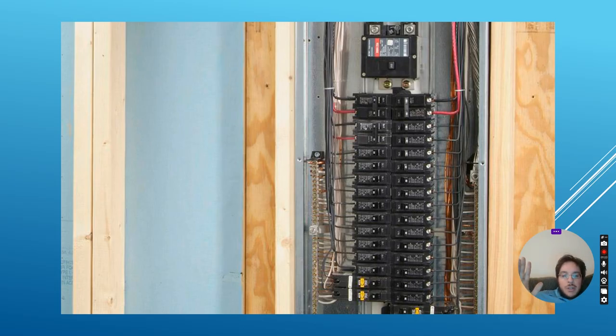Now, there's a whole bunch of different types of residential panels, and whichever one you get, ideally you want to get a 200 amp panel, and the reason is most electrical services to houses now are 100 amps, but the cost between a 100 amp panel and a 200 amp panel is like $100 or $200. Now, down the road, if you decide to add an electric car charger, and in 10 years most houses will have one probably, an electric car charger uses, let's say, 48 amps, which is half of your panel. So you're probably going to need a service upgrade to either 125 amps or 200 amps. And the cost of changing out your panel is $5 or $6 or $8,000, depending on where you are and whether you hire a professional electrician, or some guy from Kijiji or Facebook Marketplace. But it's going to be expensive.